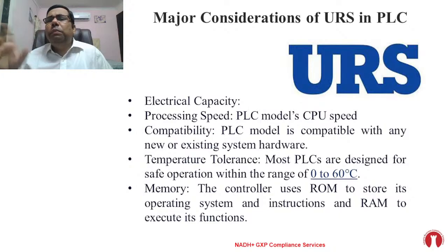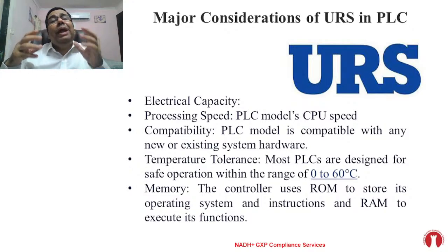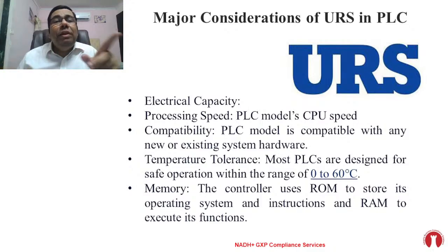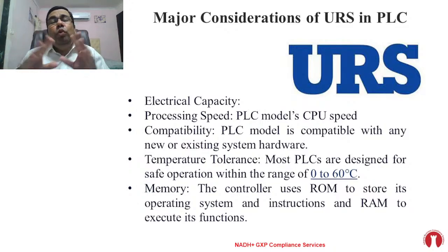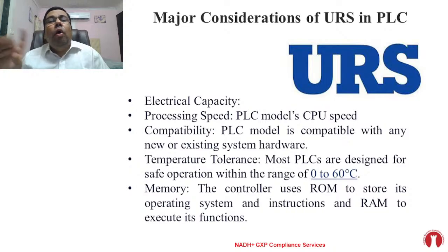Temperature tolerance - most PLCs work at 0 to 60 degrees temperature, but some reactions may take place at very high temperatures, maybe more than 150 or 250 degrees centigrade. PLCs will not work at such high temperatures. So when you have that facility, or need to run reactions at specific higher or very low temperatures, such as in biological reactions requiring extraction at minus 40-50 degrees centigrade, you need to specify in your URS that the PLC should tolerate this. Because if you use a normal PLC at a higher temperature, all the data will get corrupted.